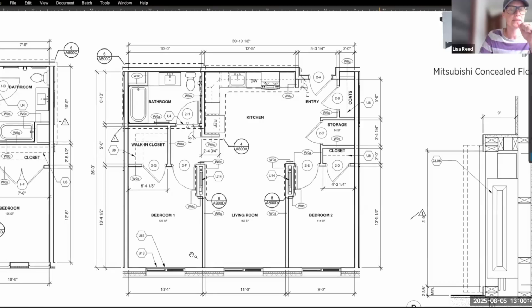The ERVs deliver the outdoor air near the walk-in closet, with another delivery point at the other closet from the bedroom, so you don't have ductwork going all over. That's a real savings in cost. Also, because the envelope is so tight, you don't have to bring all that heating, cooling, and conditioning to the exterior wall—everything stays tight back into the apartments, which reduces inefficiencies in delivery, cost, duct sealing, and all of that.